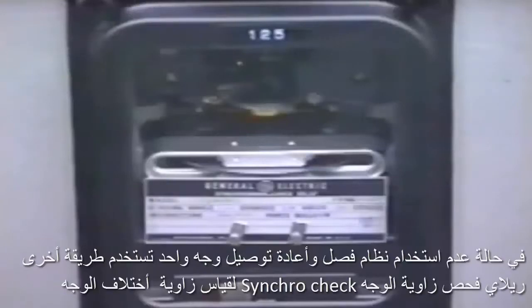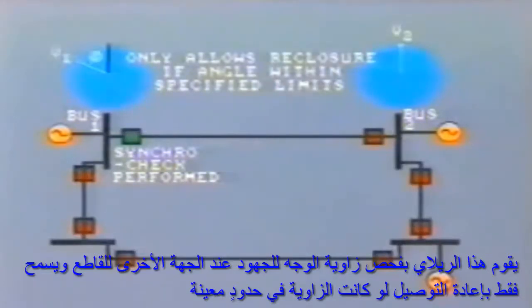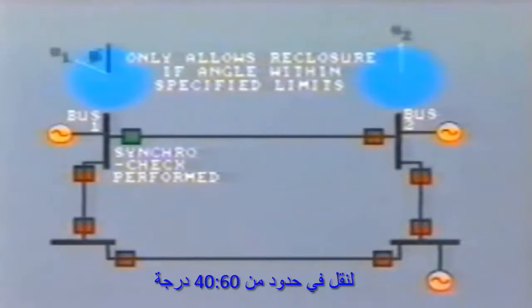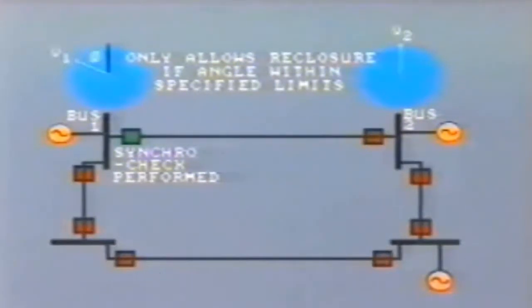If single-pole tripping and reclosure is not installed, then another method is to use a Synchro check relay to measure the phase angle difference. In this arrangement, reclosure takes place first at one end of the line only, while the Synchro check is performed at the other end. This relay measures the phase angle of the voltages on either side of the breaker, and it will only allow reclosure if this angle is within a specified limit, say up to 40 or 60 degrees out on the system.